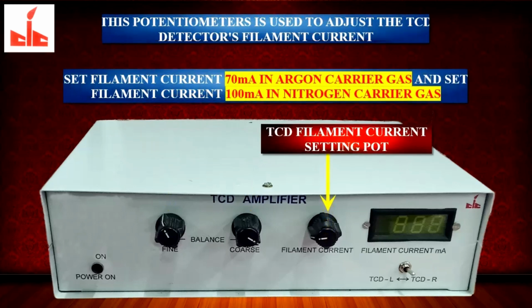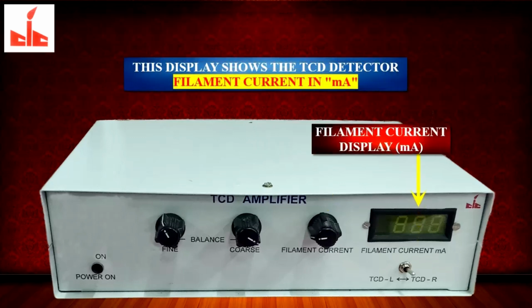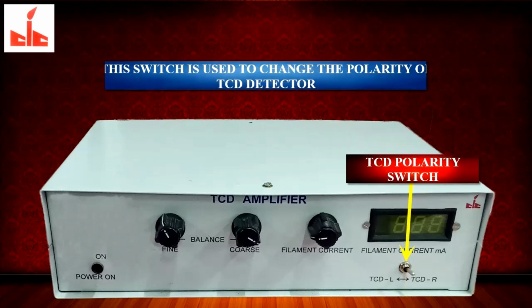This is TCD filament current setting pot. This pot is used to adjust the TCD detector's filament current. Set filament current 70 mA in argon carrier gas, and set filament current 100 mA in nitrogen carrier gas. This display shows the TCD detector filament current in milliampere. This switch is used to change the polarity of TCD detector.